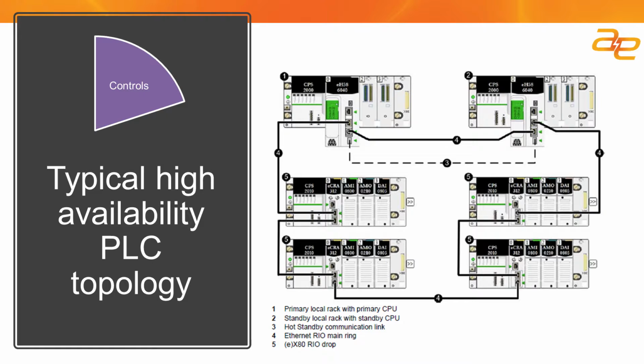A couple other things to note is that those controllers, by this dashed line, are linked by a cable which allows each of those controllers to determine the status of the other. So again, only one will be in control, but the other one will be sitting and waiting to take over control should the other present a fault or a failure. And then there's a ring. You can see the dark line that goes around to all of the I/O that forms a ring. And that ring is a distributed network that connects all of the I/O back to the controllers. And typically that ring is configured in a way that allows some redundancy within the network itself. And we're going to talk about that shortly.